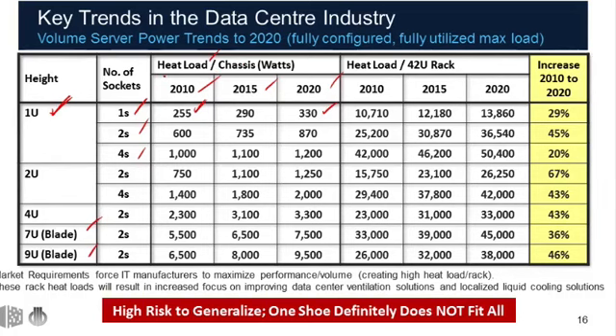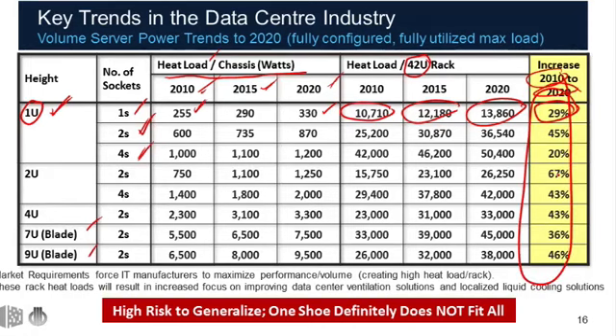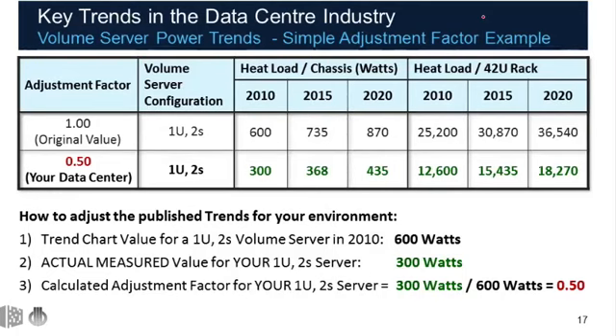So now, if we look at this per chassis, 2010, 15, and 20, if we want to multiply by 42U, if it's 1U, because a rack is 42U, here's where we get the kW: 10, 12, and 13. So what we see here is if we compare 2010 to 2020, it's a 29% increase. What's so powerful about this chart is the fact that it shows that it depends on the type of server as to the growth rate, and the growth rate goes from 29% at a low, 20% as a low, to 67% as a high. So we need to look at the individual ones in order to make that work.